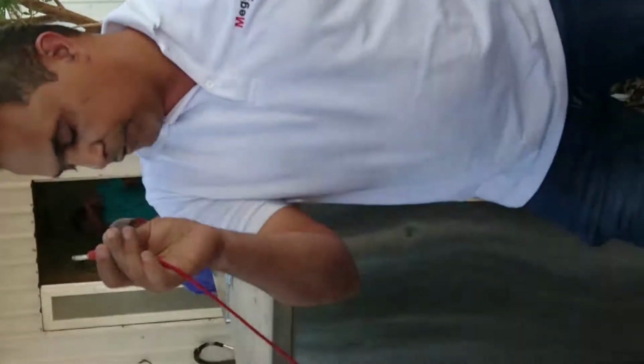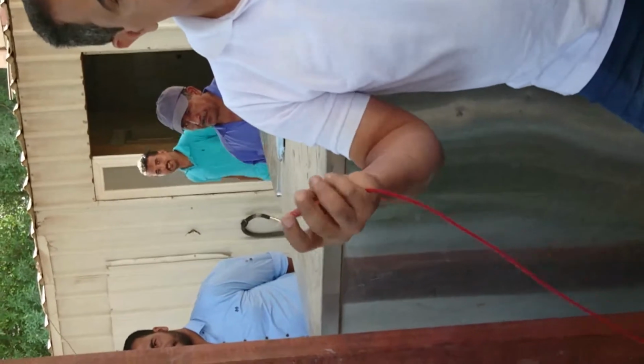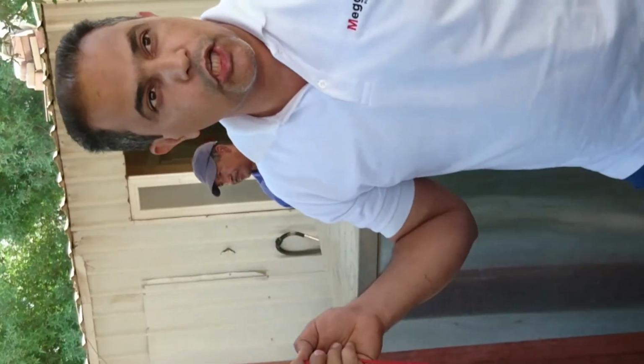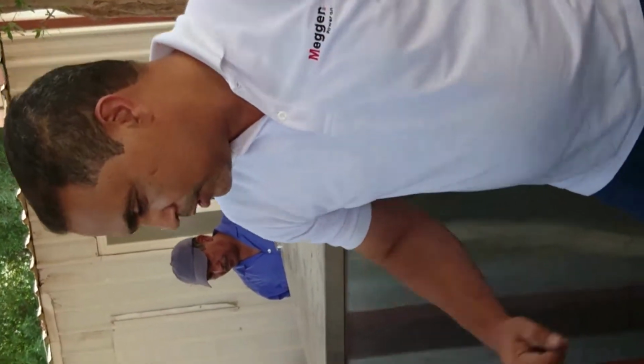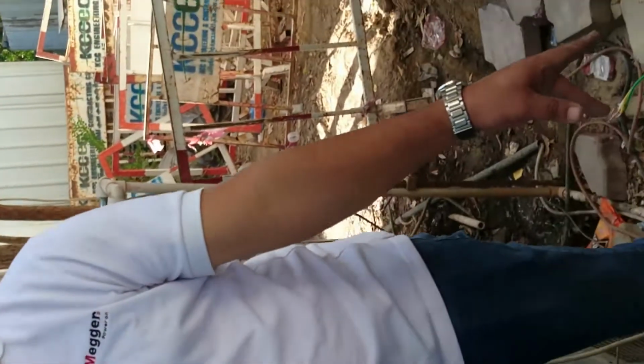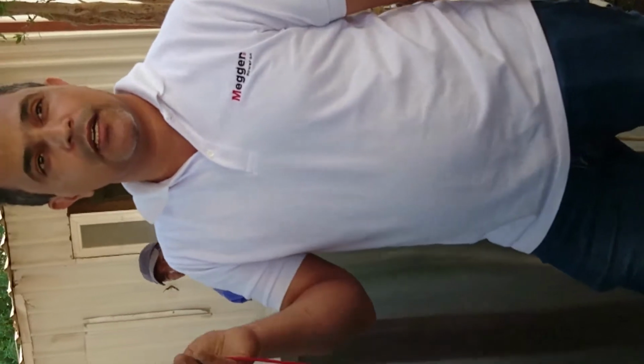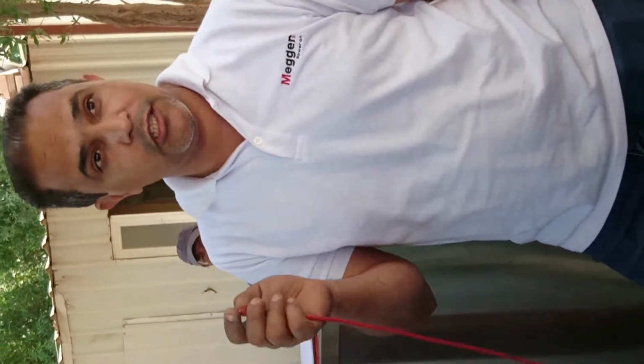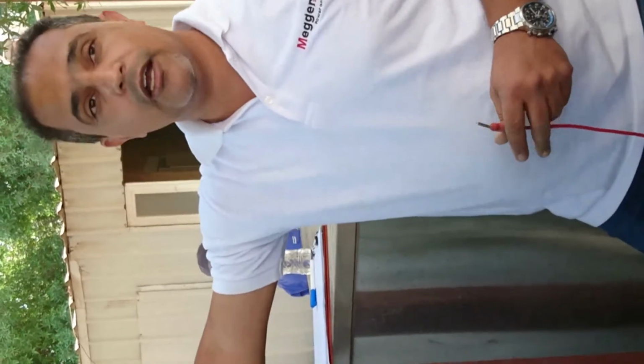What is the function of this one? This is to check the drop voltage, we call it step voltage, between the ground and the high voltage test leads. If it is more than 64 volt DC, then there will be an alarm and the high voltage will switch off.